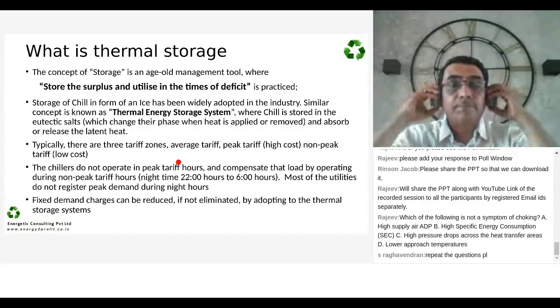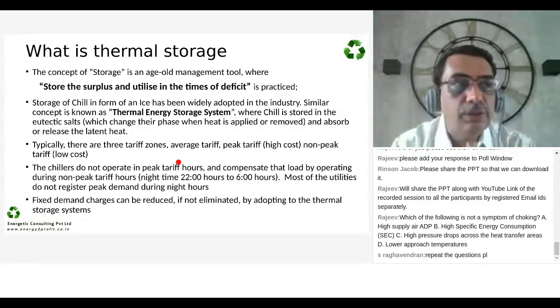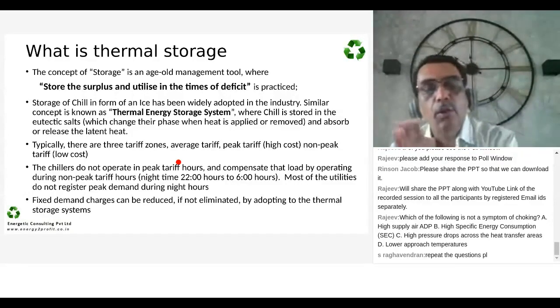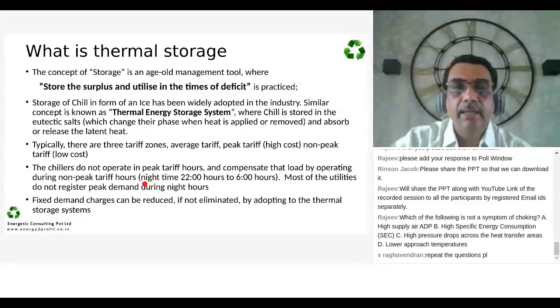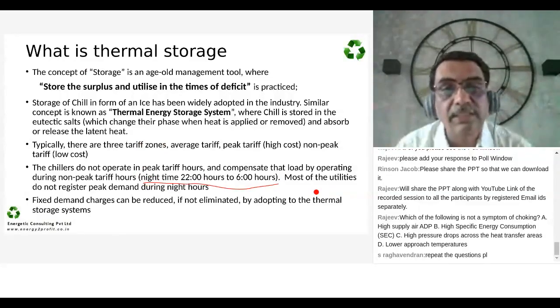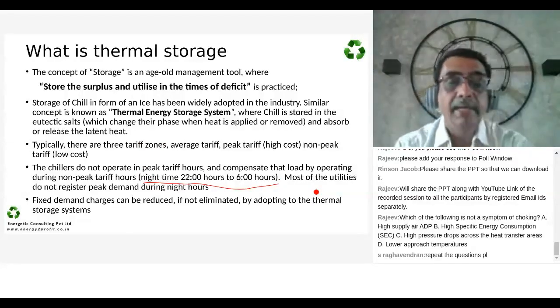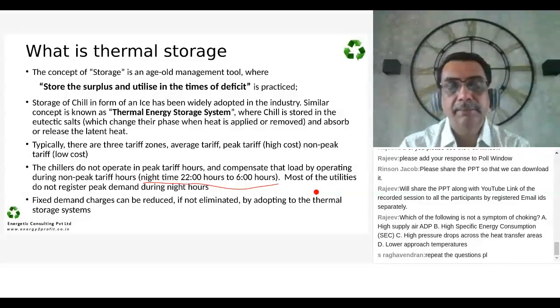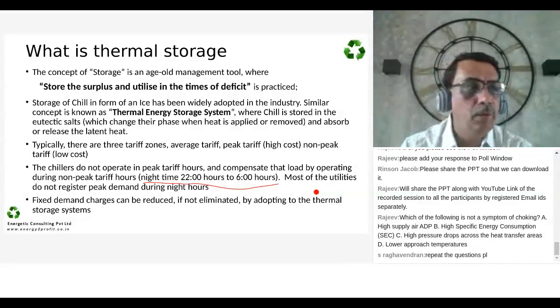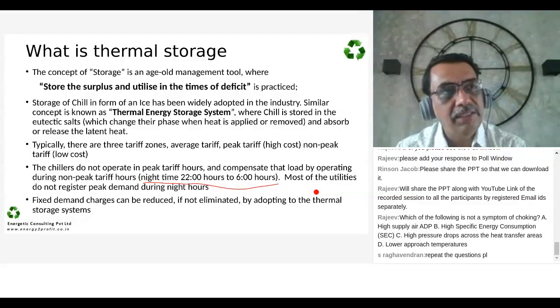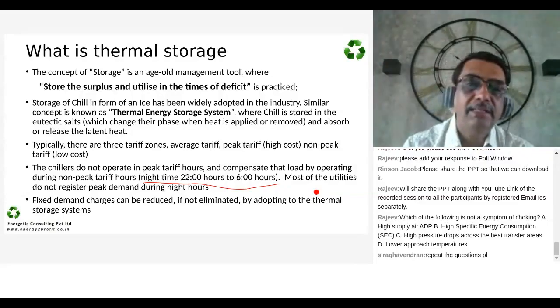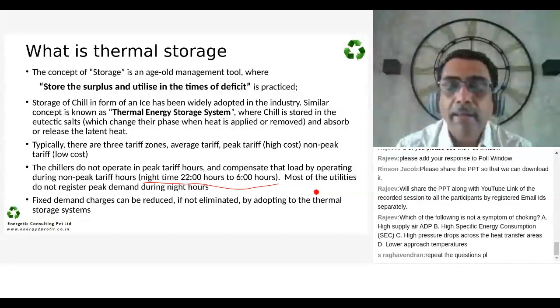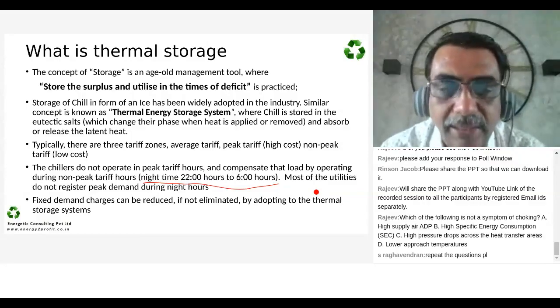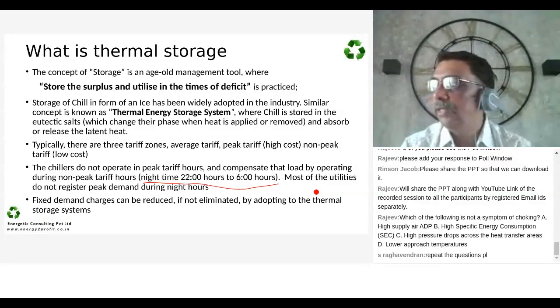Now, there is a tariff associated with your energy bill. It's not only energy. What does the tariff say? That during night time, from 22 hours to morning 6 hours, most of the utilities do not register peak demand, and also there is a rebate for nighttime use of energy. Now all our commercial buildings operate during the day. So at night what happens? The energy demand is zero. So when you have the lowest tariff, your energy demand is zero. Second, you have a fixed demand charge per month for any half an hour maximum demand registered in the system. That is called the KVA charge, popularly known as demand charge.